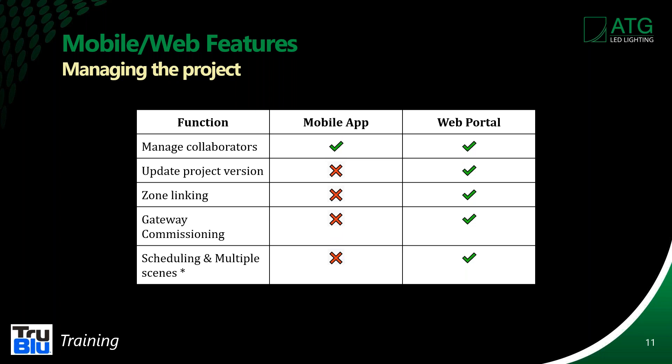There are a lot of things that can be done on the portal that can't be done on the app. On the app you can manage collaborators, but things like updating a project version, zone linking, and gateway commissioning can only be done on the portal. The gateway is required to transmit information over the internet, so you'll need a gateway for any remote monitoring or data mining. On the web portal you can do scheduling and set up multiple scenes.